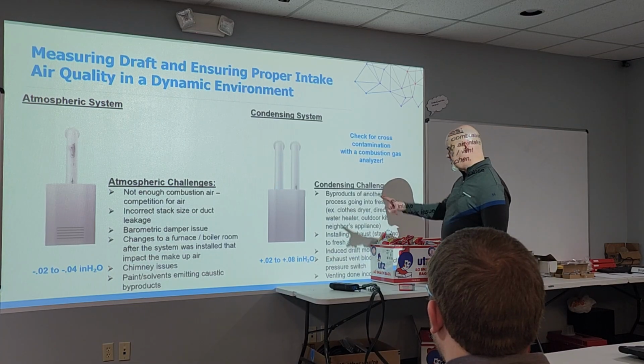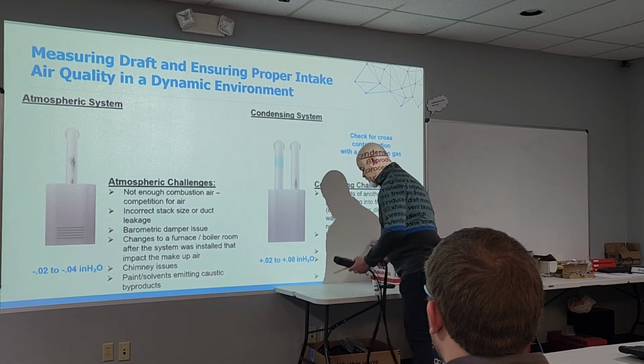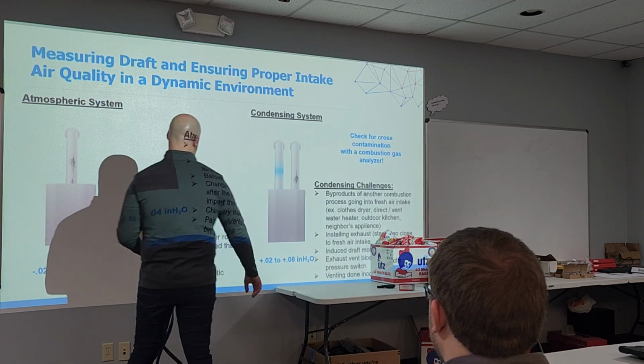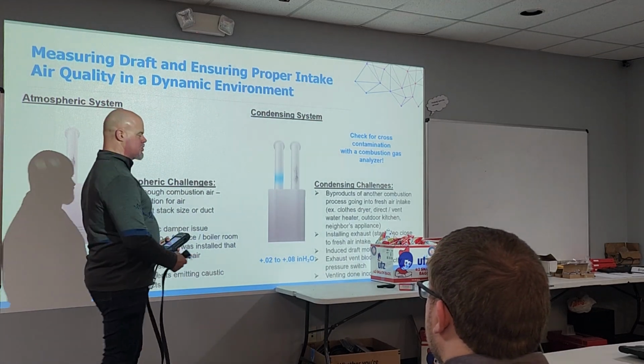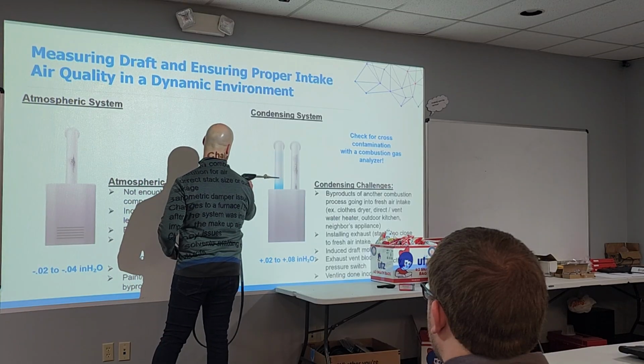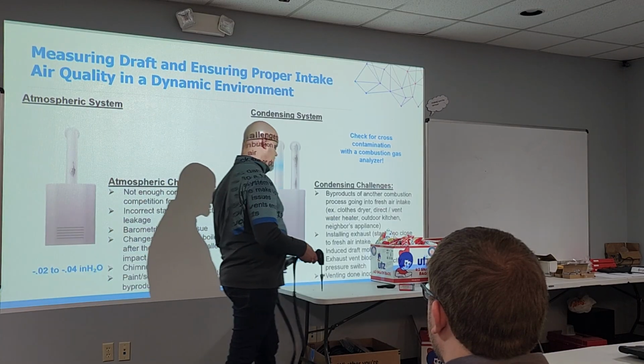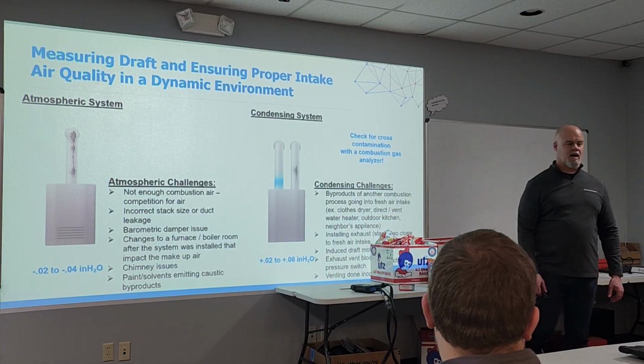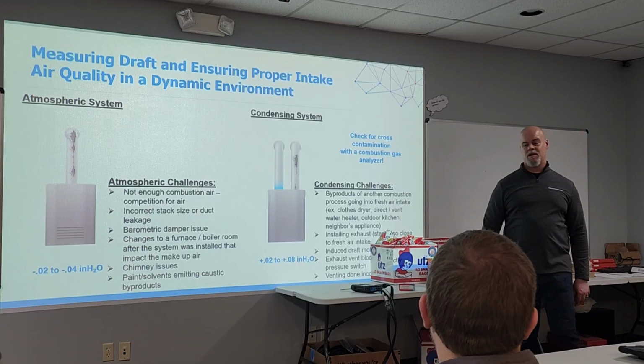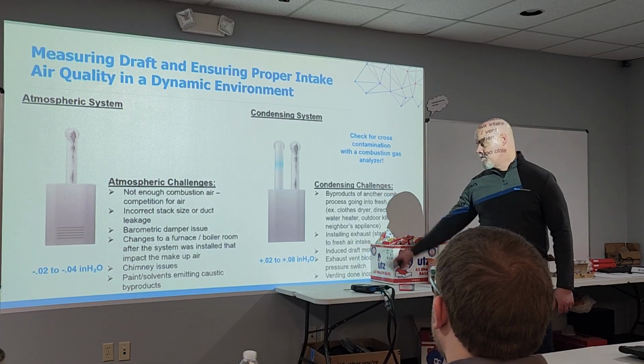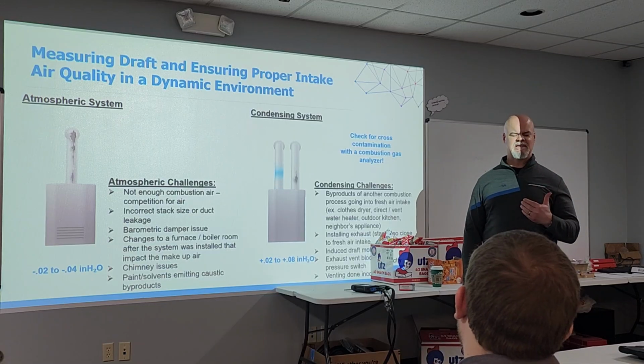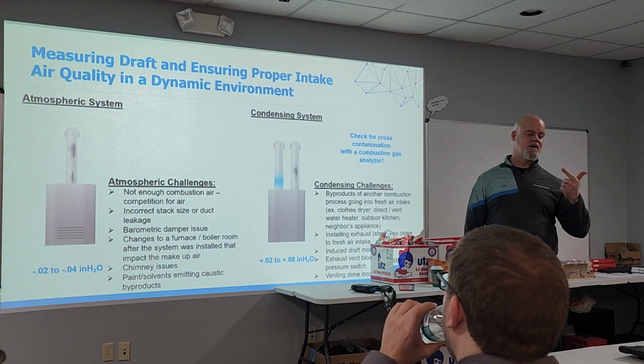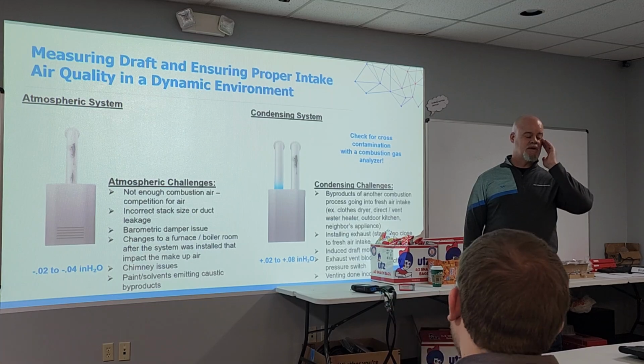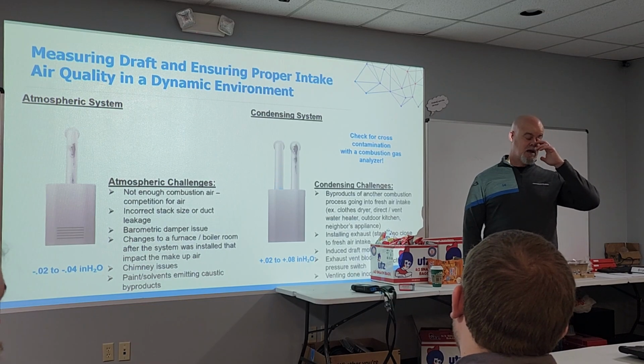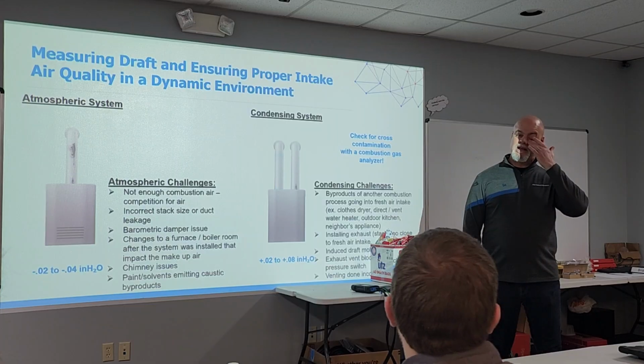The one thing I want to get across is this. Over here, fresh air intake. Whether you're commissioning, maintaining, or diagnosing, you always want to verify, by putting your probe in the fresh air intake adjacent to where you put it in for combustion, that you have nice, pristine 20.9% oxygen coming back to that system. As you are designed to breathe in 20.9, so is this thing, and so is that one. But you want to make sure there's 20.9 coming back to that, because if it's less than that, that means you have more carbonic acid and more NOx going through there. NOx is an acidic poisonous gas. Nitric, not nitrous. Nitric oxide is an acidic poisonous gas that eats whatever it touches.